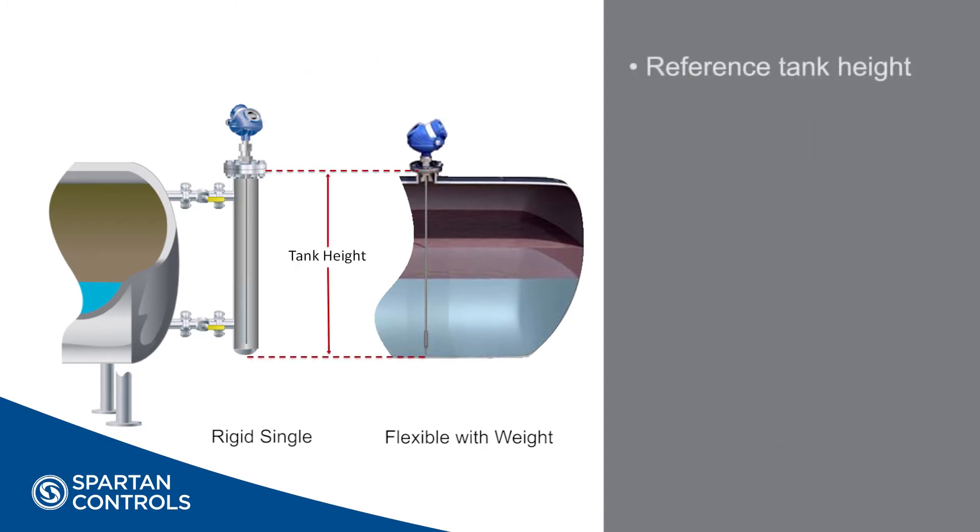Reference tank height is the distance from the flange our transmitter's mounted on to the zero reference on the tank. This is the most critical measurement you make as this is the zero reference point from which our outputs will be referenced.